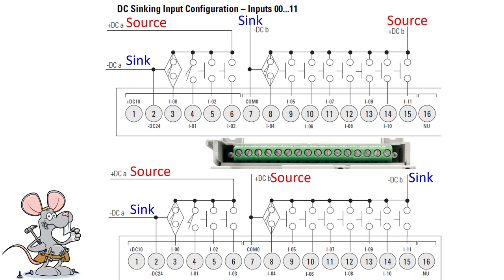Now if you're using a dry contact like we're doing, it's irrelevant because dry contacts have no polarity — they're not polarity sensitive, so it doesn't matter one way or the other. Where it will come into play is if you build a learning station and use some extra terminals for outputs or inputs not connected to the simulators — just going to a terminal block where you can hook up your own sensors and field devices for your own learning experience. Then it matters, because you have to know what you can do with sinking and sourcing.